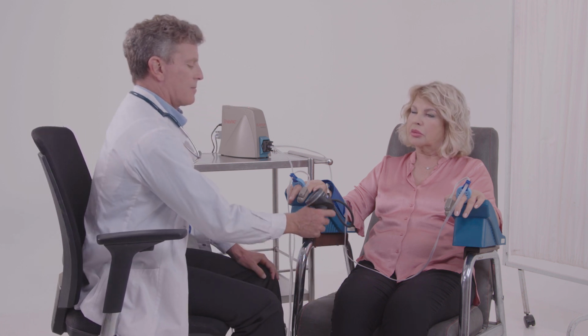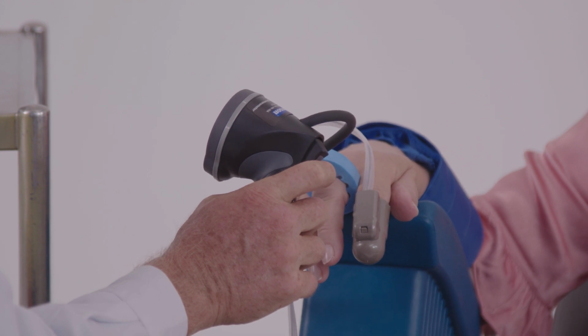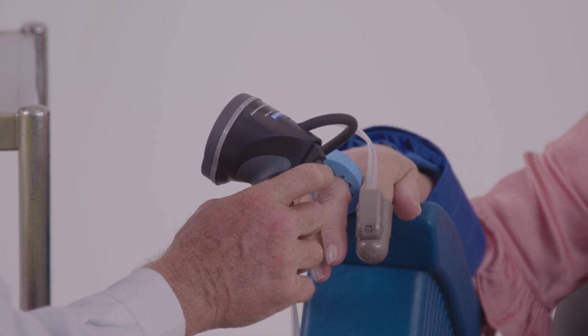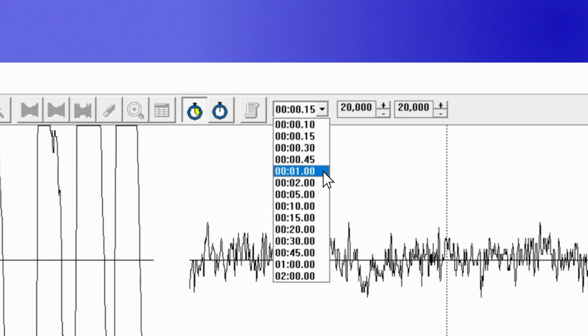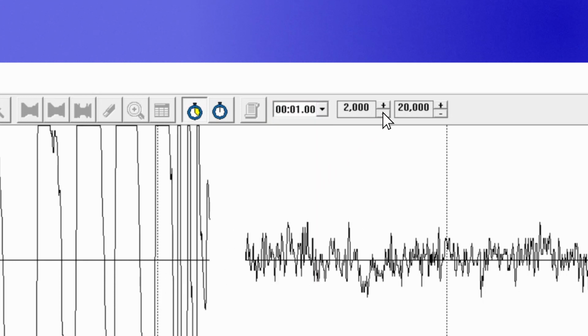Inform the patient you are about to release the occlusion. The study is not yet over, and the patient must remain still. Exactly after 5 minutes, release the cuff's pressure. Click the timer icon to reset the time. Set the gain back to fit the screen and the time to 1 minute.